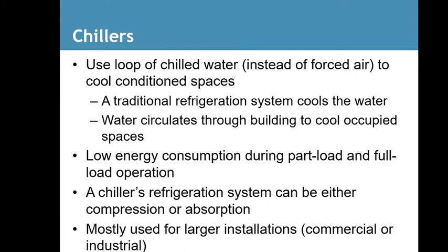But with a chiller, it's much more economical to heat and cool water that runs to coils within a large building, something like the Empire State Building. Every 10th floor has chilling systems on it, so that they don't cool more than 10 floors at a time. This is traditional for refrigeration. It cools the water, and water circulates through the building to cool occupied space. Low energy consumption during part load or full load operations. Chiller refrigeration systems can be either compression or absorption. Mostly used for large installations, commercial or industrial.